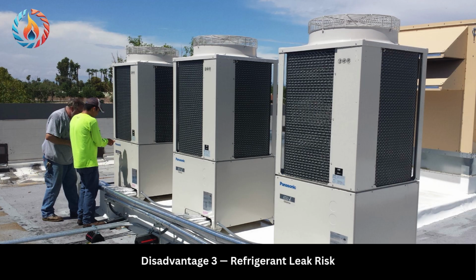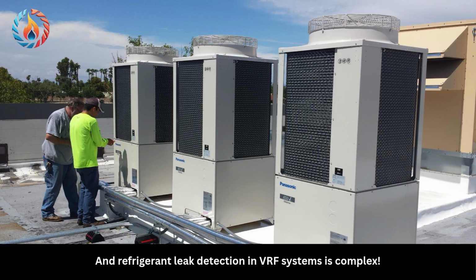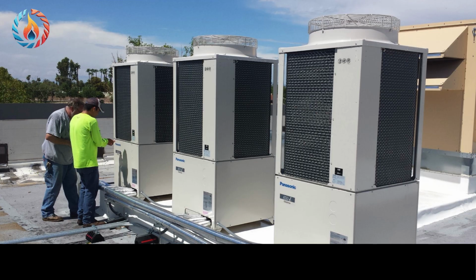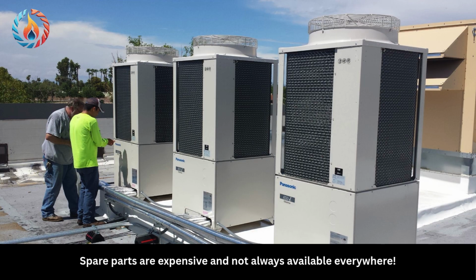Disadvantage 3. Refrigerant leak risk. Since refrigerant pipes run throughout the building, a leak anywhere affects the whole system, and refrigerant leak detection in VRF systems is complex. Disadvantage 4. Expensive repairs. If the outdoor unit or inverter compressor fails, repair cost is very high. Spare parts are expensive and not always available everywhere.